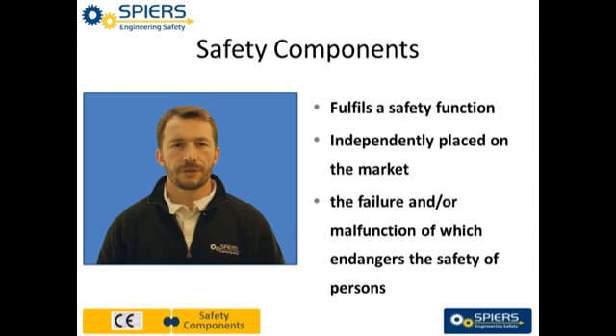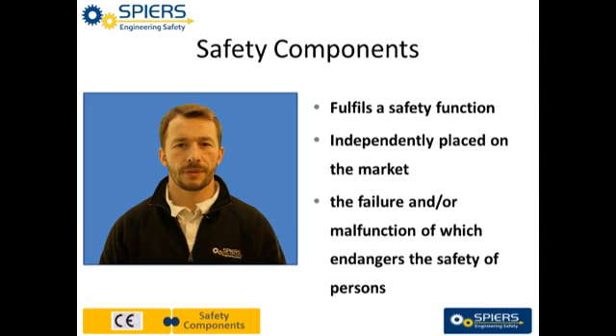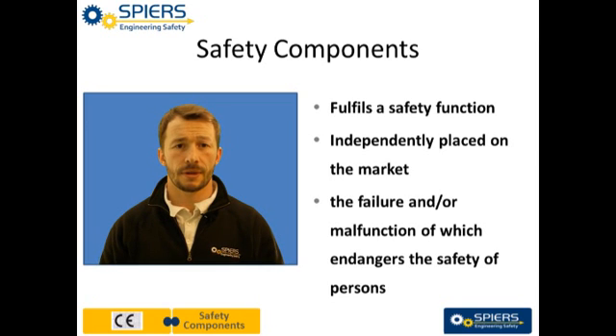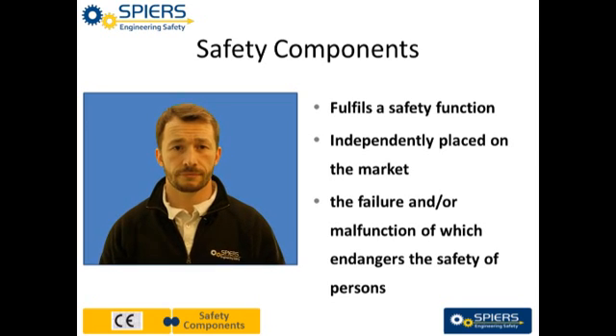During the design phase you must identify safety components within the machine. These are any component of which the failure can result in an unacceptable increase in risk and which you did not manufacture yourselves.